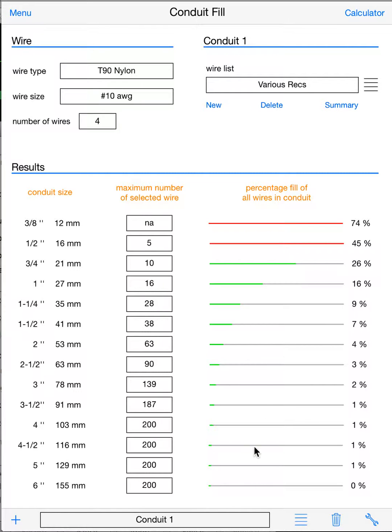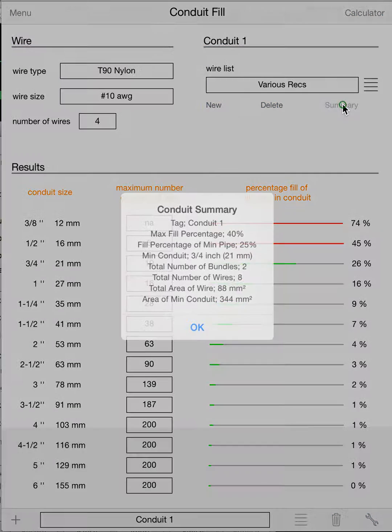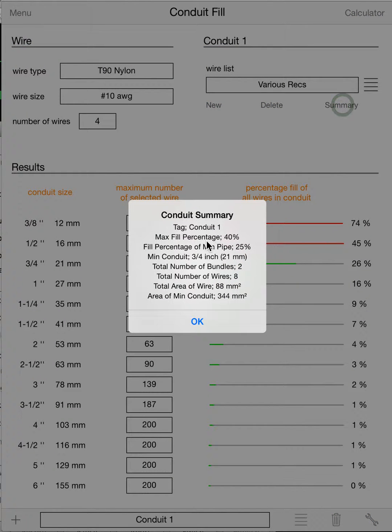Now you can see your next conduit, three-quarter inch, is 26% full. This pipe is going to work, and of course any larger pipe will also work. You can also get a summary of what's in the pipe by clicking on summary.